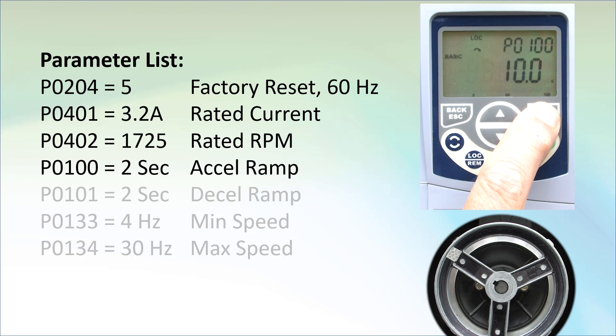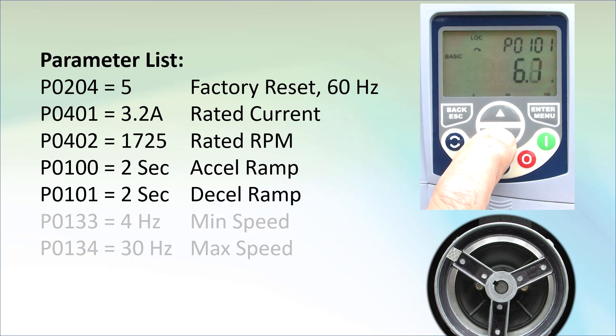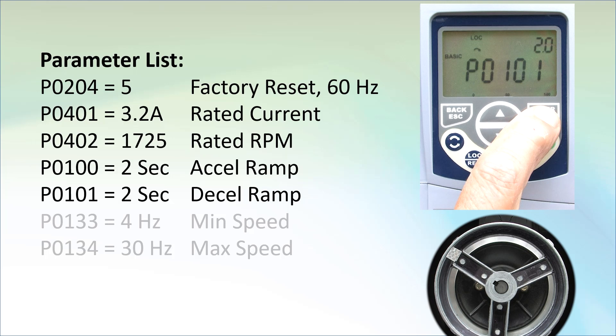Enter to change it. This motor doesn't have any load on it so let's change the acceleration to something really short to help speed up the video. How about 2 seconds. Enter to accept. Up arrow to deceleration and change it to 2 seconds too. Just so we don't have to wait a long time for the motor to spin up or down during the video.